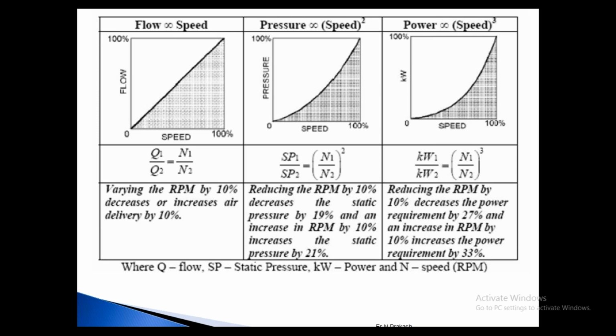Ultimately, it is not only about saving energy. Energy efficiency should be the maximum. Energy efficiency means that for the same output, your power cost is less. In the humidification plant and air conditioning, you attend various energy programs, or hear from different manufacturers and suppliers. They will tell you their equipment is highly efficient, this pump is very good, this motor is good, you can put a VFD. All these things they will tell. But unless you know the system, how it works, how it performs, and what the basic requirement of the customer is, which one to use, without this knowledge we can't solve it.